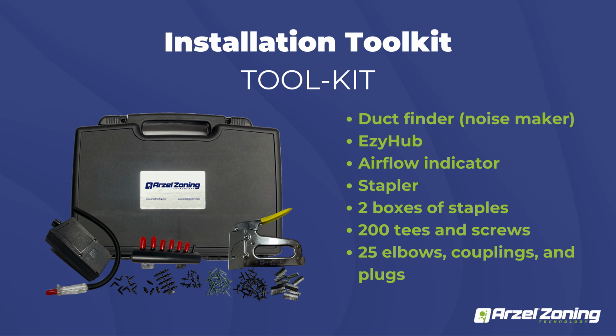It's used with our internal mount dampers. It basically acts like a manifold for your tubing. So when you come out of your ductwork with all those insertable dampers with 5, 10, 15 different tubes, it just gives you a nice clean spot to plug those tubes to and bring those back to the panel. So it kind of acts like a manifold would on a boiler. It just gives you a distribution reservoir. That's really all it is.